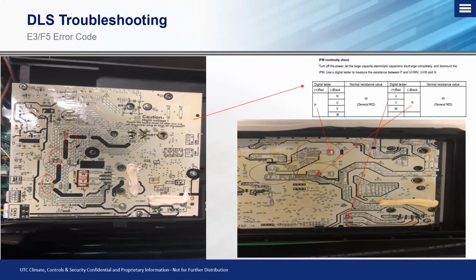Okay. Another really good indicator with this type of board that we see on the left here, there are a green and a red light that will be illuminated when this thing has power. Now it's hard to see on this board, obviously, because it does not have power, but if you follow my cursor right down here, this little square down here, there's a red and a green light. If you can confirm that you have power to this board, which you would check right up here, L and N, that's AC power coming in, you take your meter across here and verify that your incoming voltage is appropriate to the board.